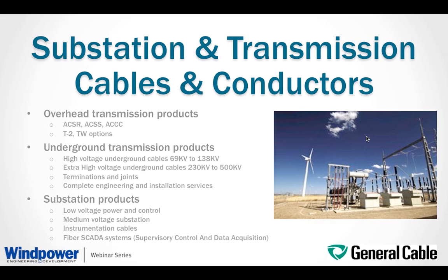Those more specialized constructions can offer various benefits ranging from higher ampacity rating, smaller diameter, or better thermal characteristics. And then on the underground side, high voltage and extra high voltage cables, normally ranging from 69 to 500 kV, can also be used. These would normally involve a turnkey project where complete engineering and installation services are provided with the cables, terminations, and joints. Then there's a number of other constructions such as low voltage power control, medium voltage, instrumentation cables, as well as supervisory control and data acquisition systems that are used in the substation.